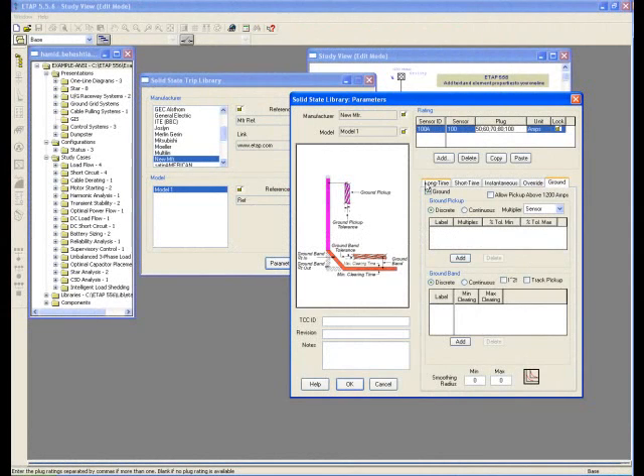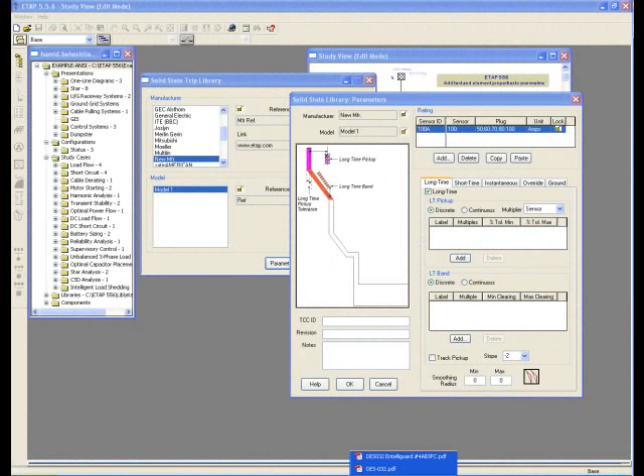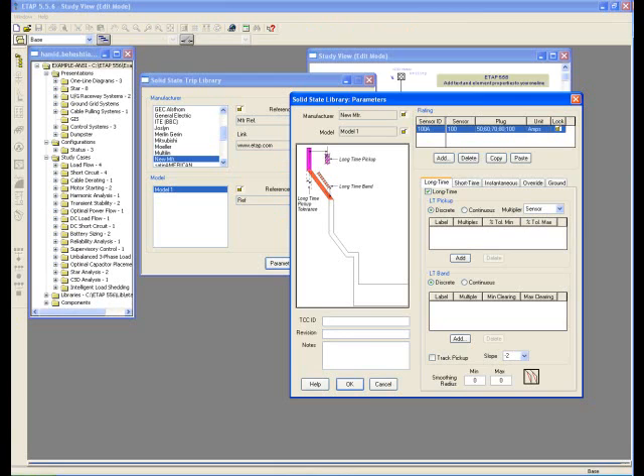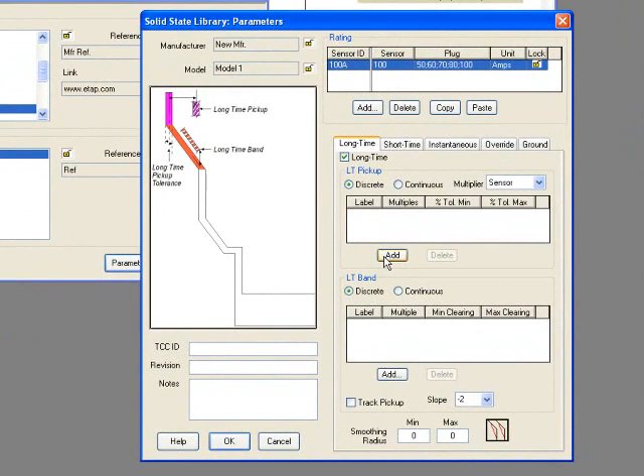As you can see in this manufactured TCC, this is your Long Time Pickup. The Long Time Pickup comes with Pickup Value and Pickup Tolerances. Sometimes it's discrete settings, like in this case. If you click on Add, you must enter a new label for this setting.